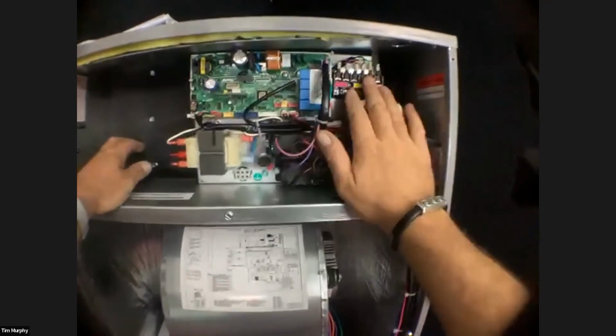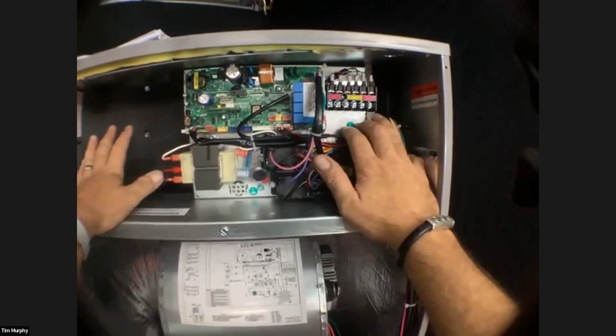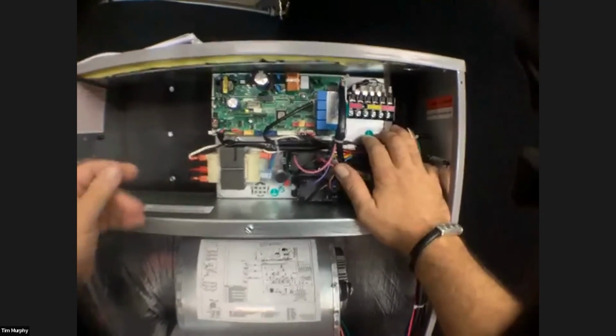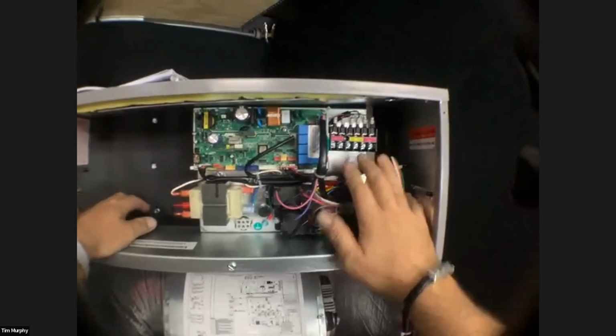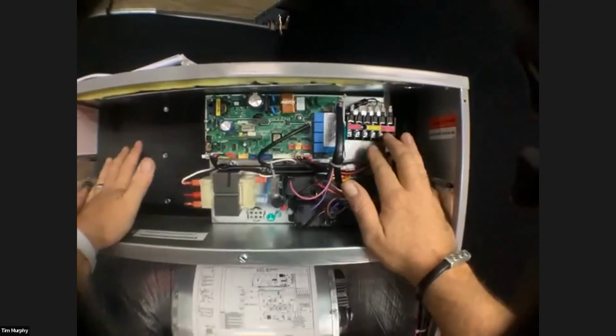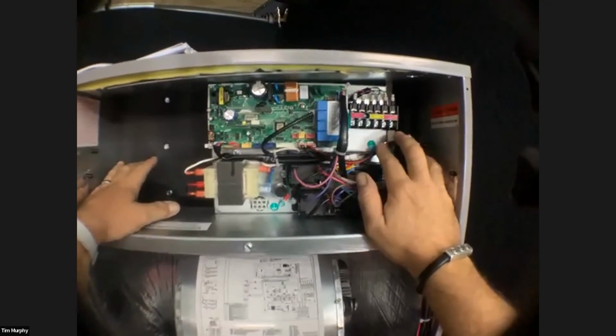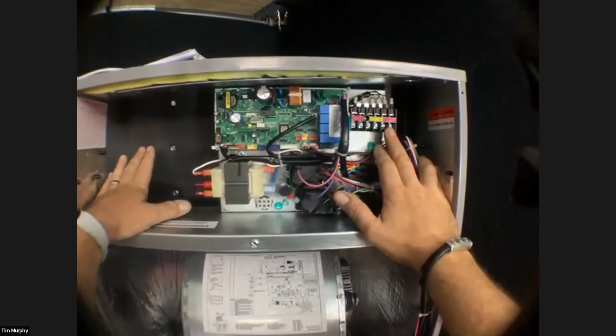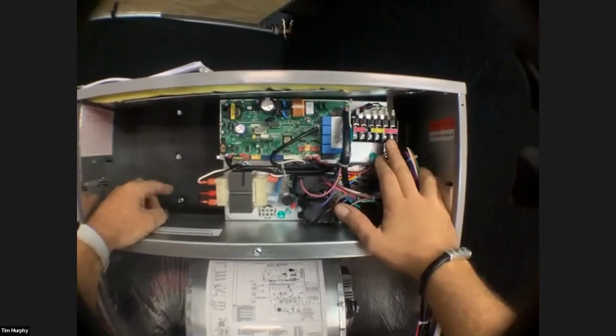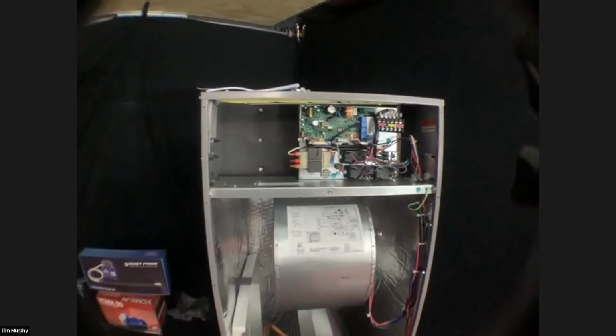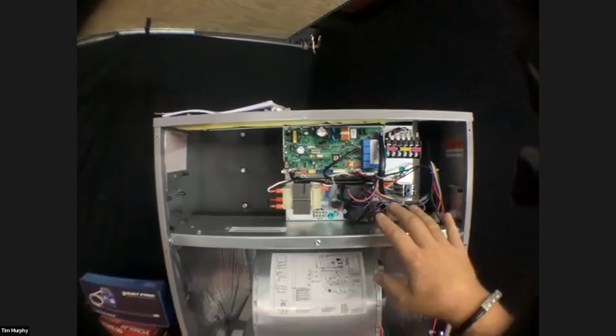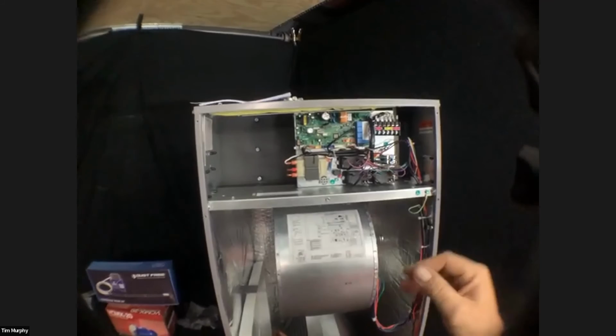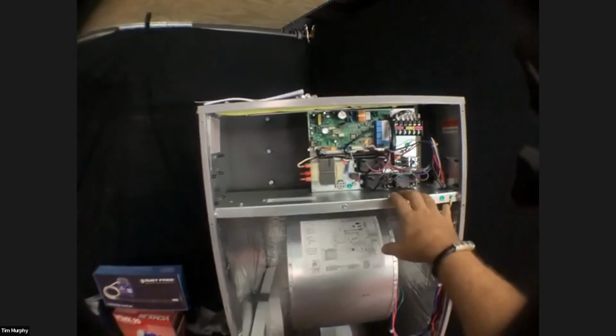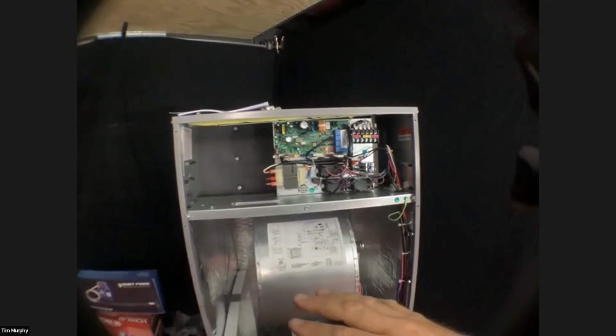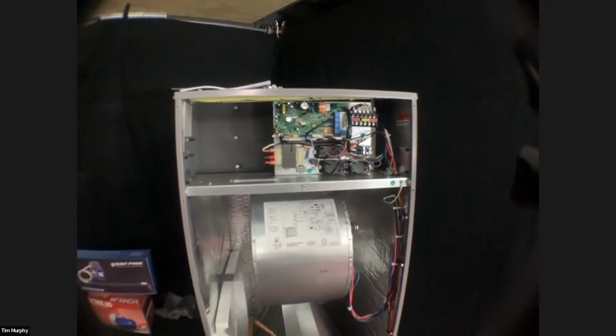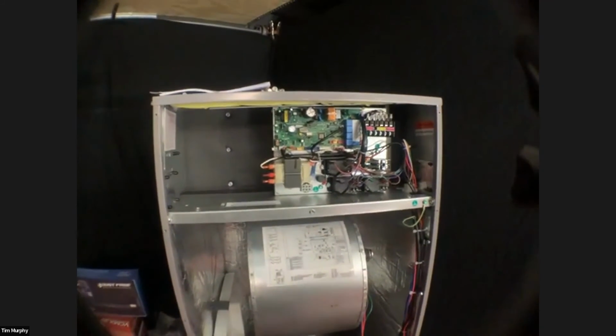If you have two systems and you want to operate them on one advanced wire controller, you can. That's another benefit, and it may be application based. If you have two of these systems in a single zone application, like cooling an IT room, and you want both systems to come on together, you can daisy chain both of these systems off the F3 and F4 and control both systems, or three systems if you have three, off one wire controller. That would be a benefit in an IT room, if it's a long room. This not only applies to the multi-position air handler, but also to the high walls. The high wall systems will need additional accessories, but with the four-way cassettes, the multi-position air handler, and the ducted systems, you can run multiple systems off one wired controller. That's definitely something I could have utilized in the past.